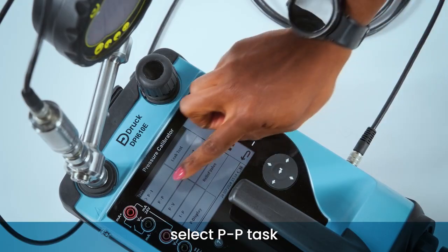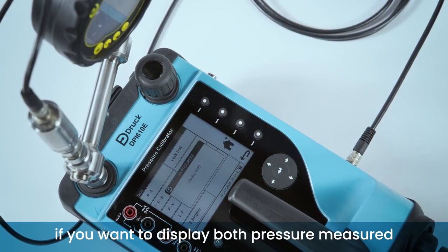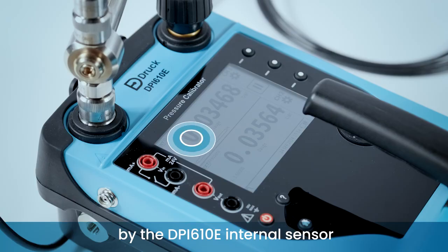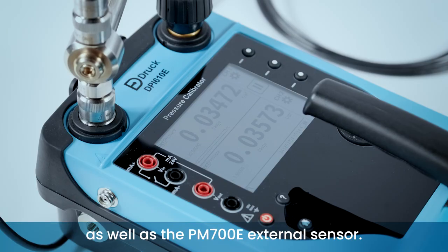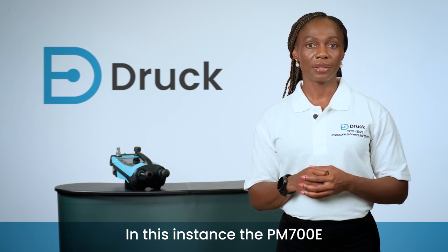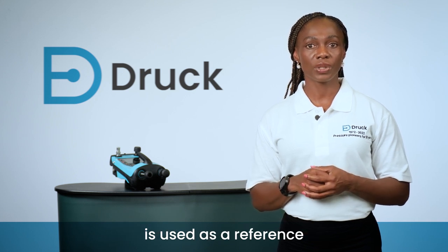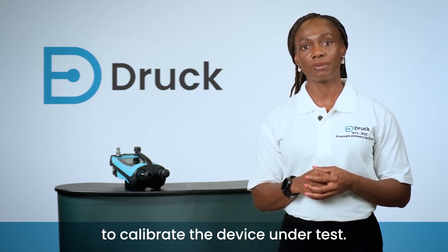Select P-P task if you want to display both pressure measured by the DPI610E internal sensor as well as the PM700E external sensor. In this instance, the PM700E is used as a reference to calibrate the device under test.